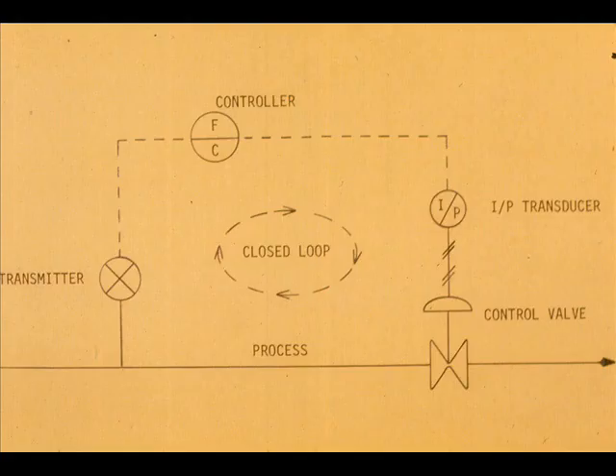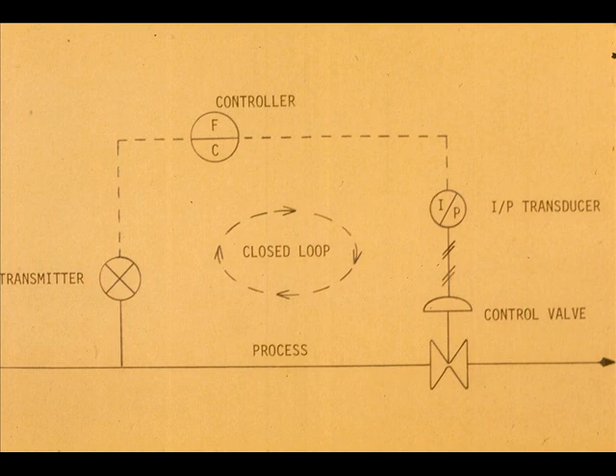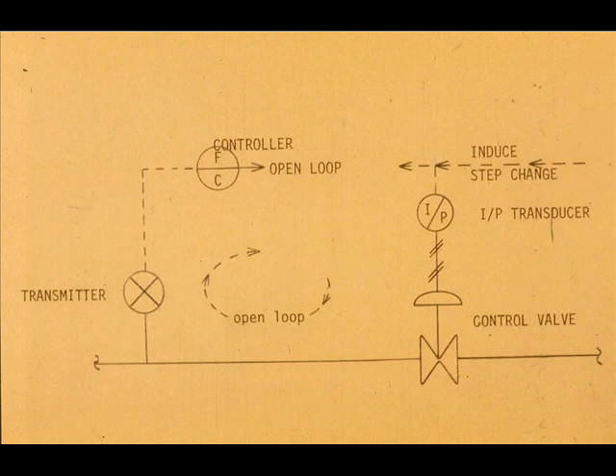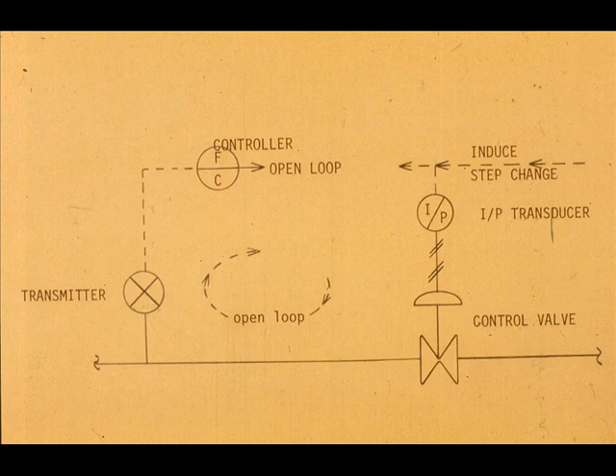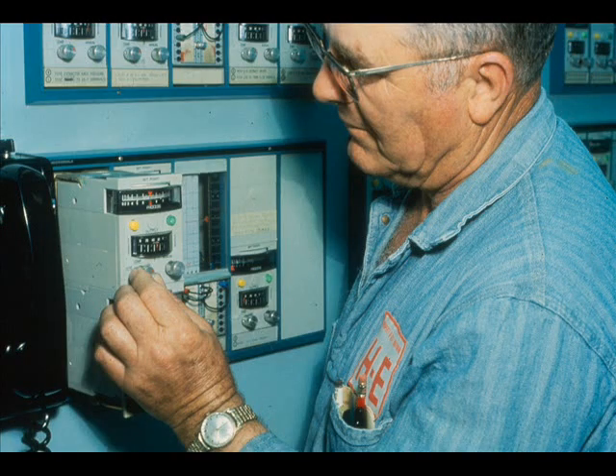The process curves we have shown are those made by closed loop control. Much information about the process is revealed by observing its reaction to a step change while in open loop status. This means the control valve stem position remains stationary while the pen moves across the chart. This can be done by placing the controller on manual.